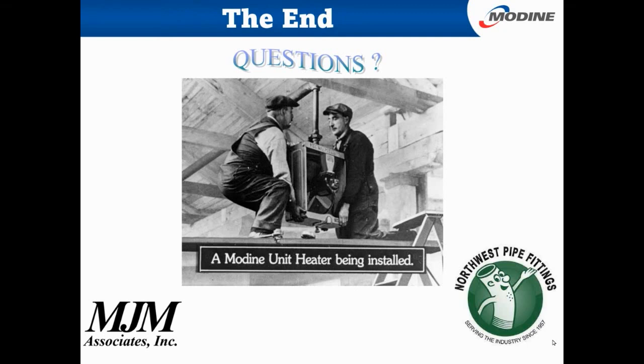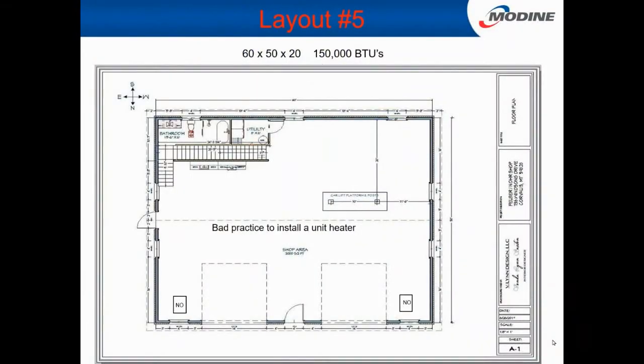Now, as far as air changes go, that one is normal. But if you get a building like the one we just looked at back there, where the garage doors are open and closed all the time, it's a mechanic shop. Sometimes that air change has to be way higher, because when you open that door, cold air comes in. So you might have to have it high, like 10 air changes.